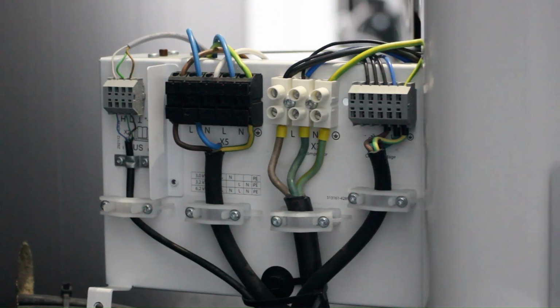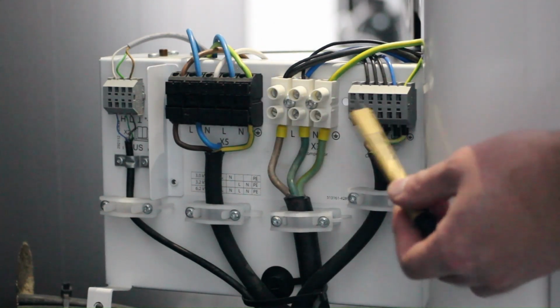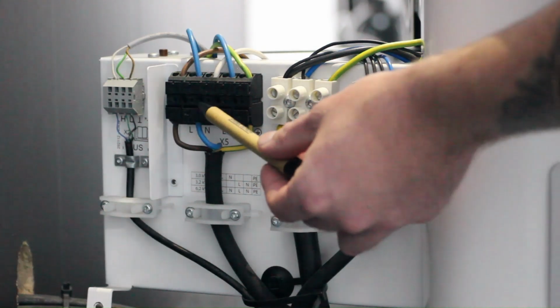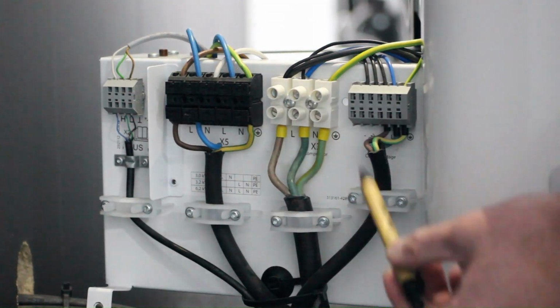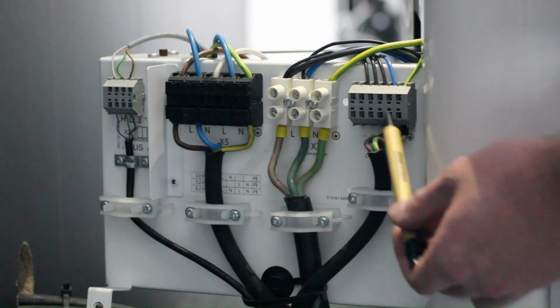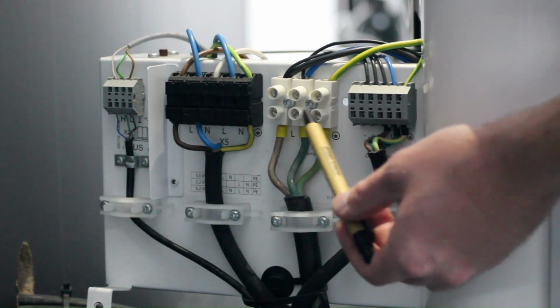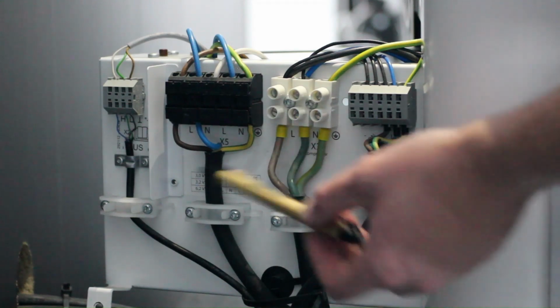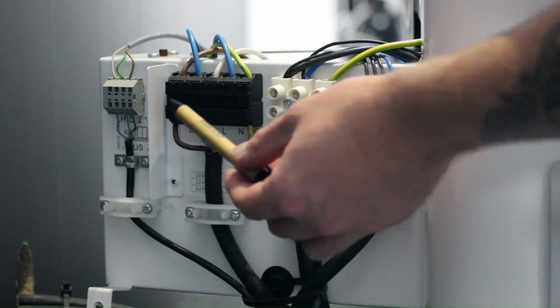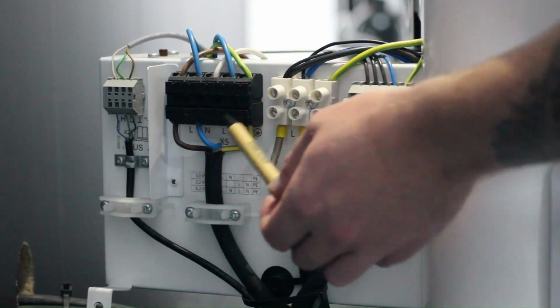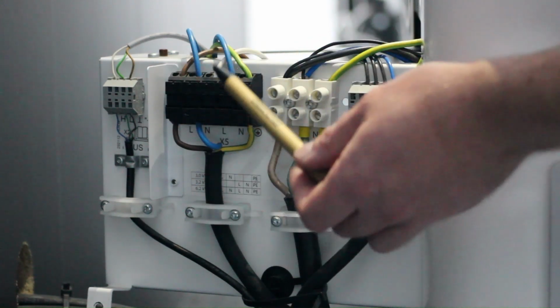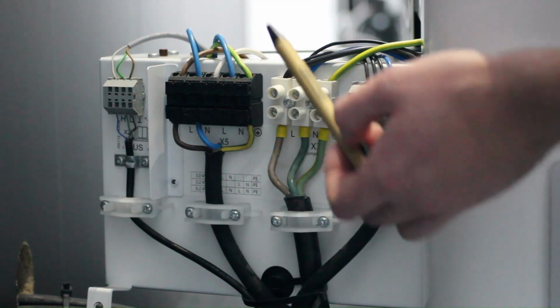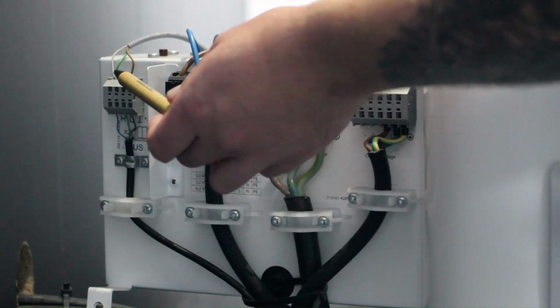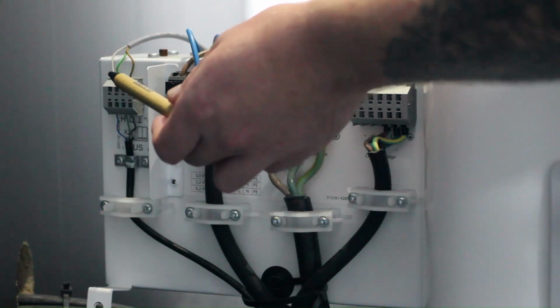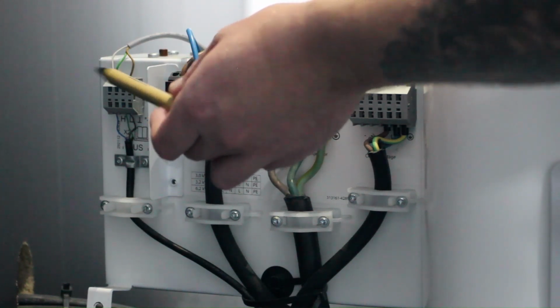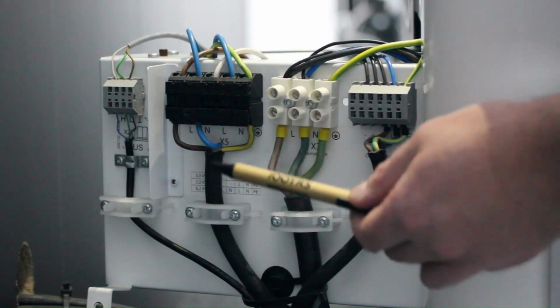For electrical connections, we have our controls, our compressor, and our onboard booster heaters. We'll need to bring a 16-amp supply to our controls, a 32-amp supply to our compressor, and either one or two 16-amp supplies to our onboard boosters, depending on how many kilowatts you are using. You also need a Cat5 or Cat6 screened data cable. This is our communication cable, which runs from the outdoor unit to our WPM controller.